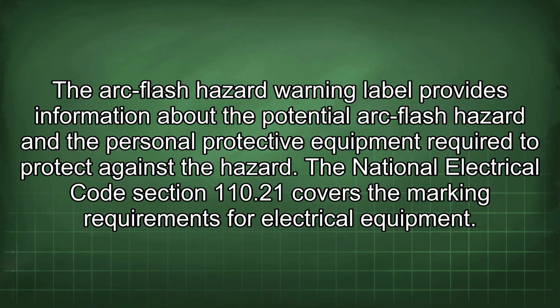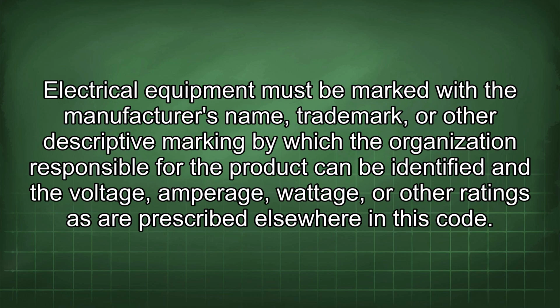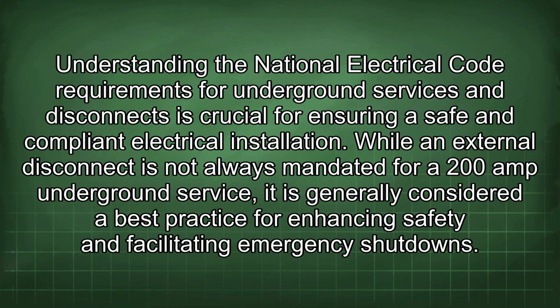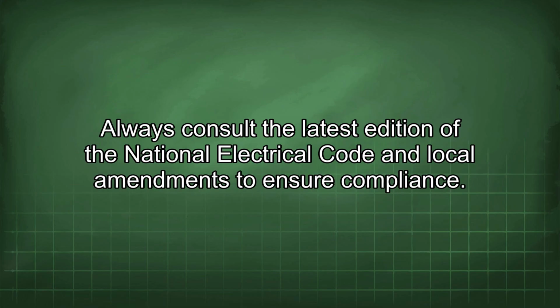The National Electrical Code Section 110.21 covers the marking requirements for electrical equipment. Electrical equipment must be marked with the manufacturer's name, trademark, or other descriptive marking by which the organization responsible for the product can be identified, and the voltage, amperage, wattage, or other ratings as are prescribed elsewhere in this code. Understanding the National Electrical Code requirements for underground services and disconnects is crucial for ensuring a safe and compliant electrical installation. While an external disconnect is not always mandated for a 200 amp underground service, it is generally considered a best practice for enhancing safety and facilitating emergency shutdowns. Always consult the latest edition of the National Electrical Code and local amendments to ensure compliance.